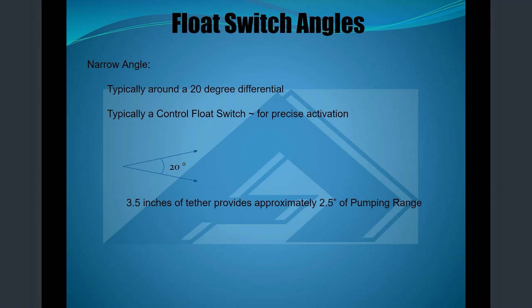So control float, you typically measure 3.5 inches, and that would be your tether point, whether it's on a cable weight or tethered with your rubber locks or your stainless steel pipe clamp, and that's just where it's set. And then depending on where it activates, this is a pump switch, and it should be wide angle. Yep, this is a wide angle. So you can kind of hear that ball click here, which is about 45 degrees above horizontal. And then as it comes down, it deactivates about 45 degrees. So you got a total 90 degree differential, but with the tether here, that's your off here and your on's here. That's only a couple inches of activation angle.